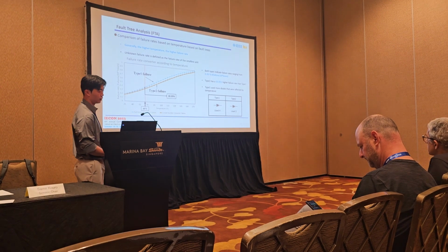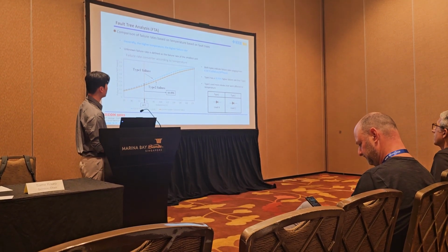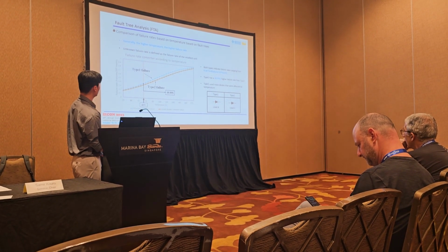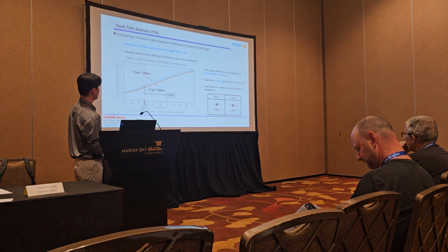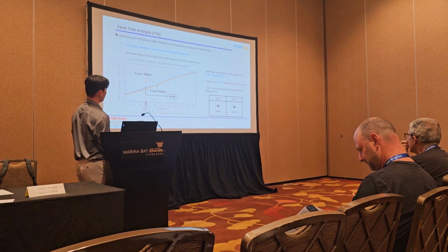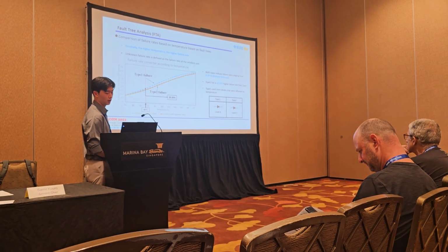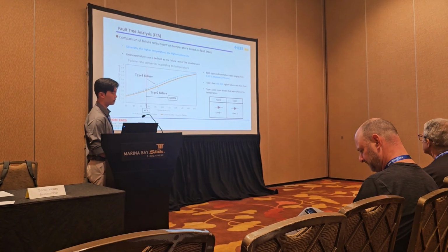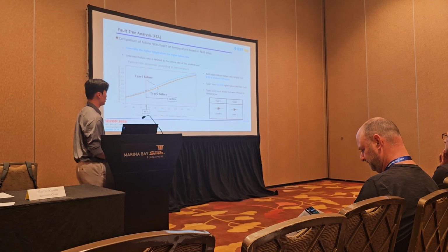And then we analyze converter failure rates based on temperature, based on the fault tree. Look at the graph. We can see that generally the higher the temperature, the higher the failure rate. And also at 65 degrees, type 1 has about 10% higher failure rate than type 2. This is because type 1 used more diodes that were affected by temperature. The table below shows how many diodes each converter used. Type 1 used 4 diodes and type 2 used only 2 diodes.